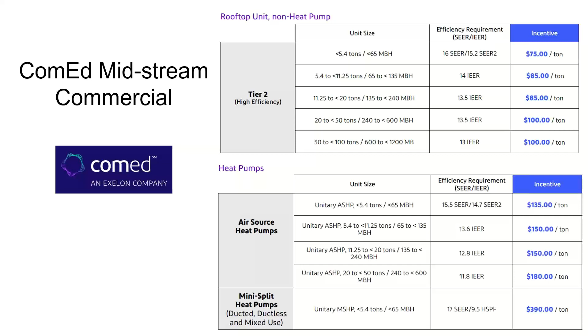And then mini splits are on there as well. That's brand new to the program as of like 2 months ago, I think. And it's $390 per ton for a mini split if you hit the efficiency requirements, which is a fantastic rebate. And once again, that's really good for combining with buildings that have hot water boilers. You let the heat pump do the heating from like 40 to 60 degrees outside. And then when it's below 40, you do the boiler to heat the building. And I'm making up the 40. It depends on each project. We can help you calculate that. I'm just throwing a number out there for example's sake.